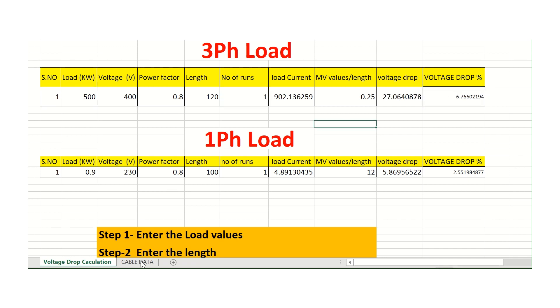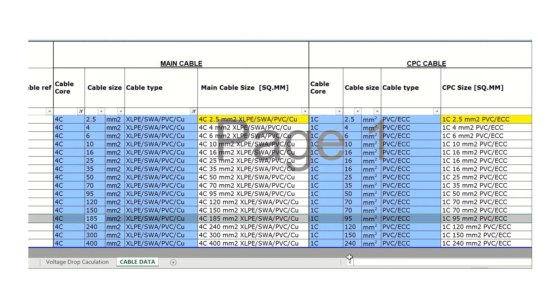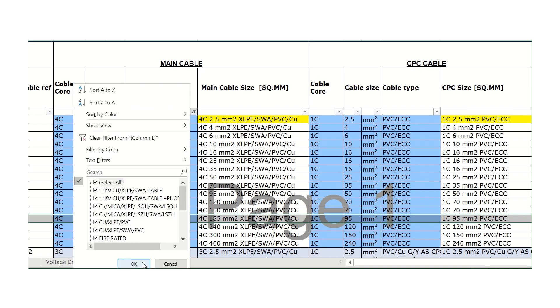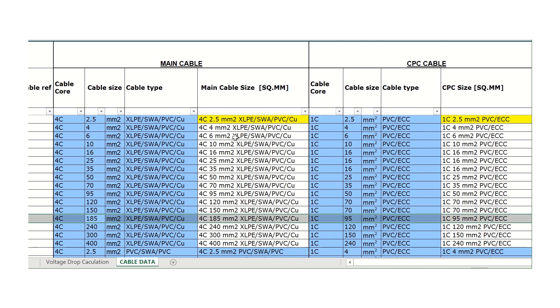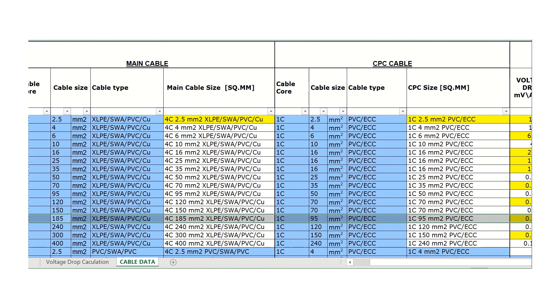The main important part is the cable data sheet. In the cable data, we have cable cores: single core, two core, three core, and four core cables. We also have the type of cables: 11kV copper, XLPE, fire rated, and MICC. For each cable, we have the main cable size, the earth cable size, and importantly, the voltage drop mV values for each cable size.